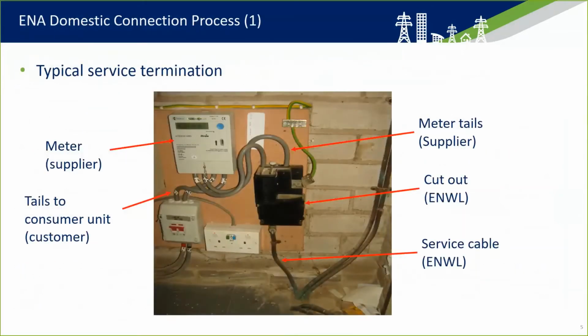This is a typical domestic service termination, just showing you the key components. So we have the incoming service cable and cutouts or main fuse, which belong to Electricity North West, meter tails and meter, which are the property of the supplier, and then finally tails going to the customer's consumer unit. The key point of the process is to identify that all of these items are rated at least 60 amps.